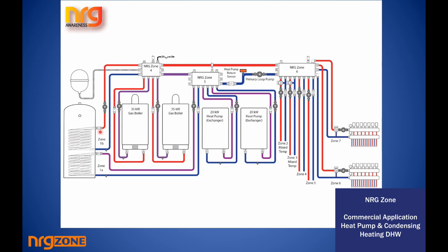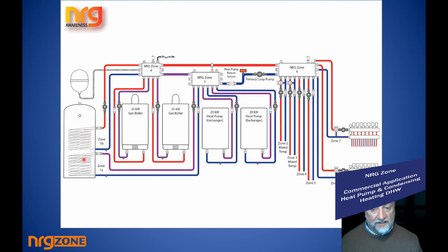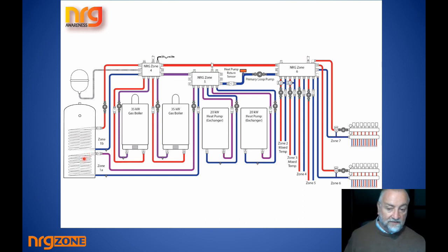Obviously you have it wired so that it won't be taking all of the energy if the coils in the calorifiers can't actually take the heat. But who knows, you might have a very large heat exchanger or a DHW system that has a big enough heat exchanger to take all of the heat and prioritize the heat.